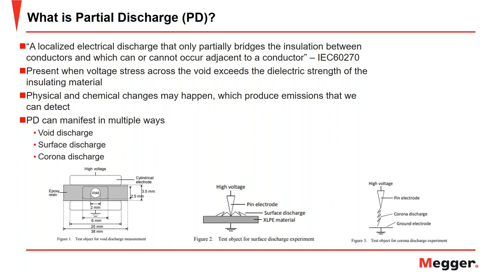And it goes on to say that partial discharges are in general a consequence of local electrical stress concentrations in the insulation or on the surface of the insulation. And generally, such discharges appear as pulses having a duration much less than 1 microsecond. And as is stated, PD activity is present when the voltage stress across a void or an insulating material exceeds the dielectric strength of the insulating material.